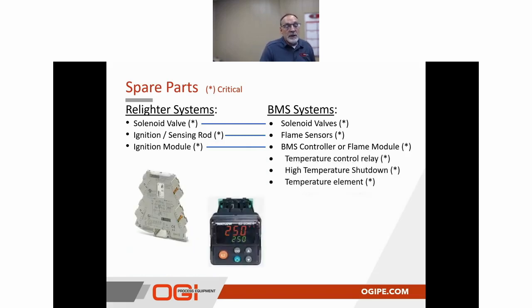The next thing we want to talk about, and this again is specific to the burner management systems or the higher end electronic systems, is temperature control relays like the one shown on the left, or maybe a high temperature shutdown, which could either be the Watlow or the control relay shown to the left. And there's also the temperature elements, which is one of those things that we inspected during the preventative maintenance side. But in the event that something is found, where maybe we have a failed element or a bad RTD, it needs to be replaced. Having that on the shelf would be helpful.